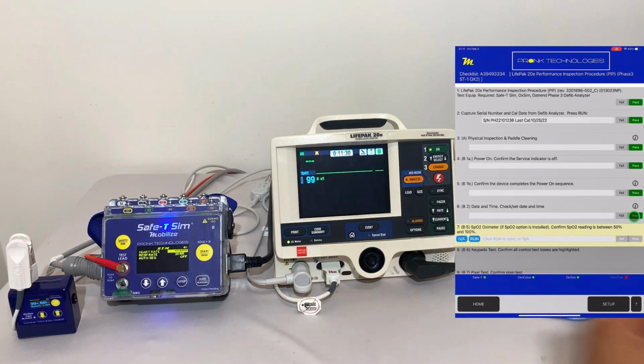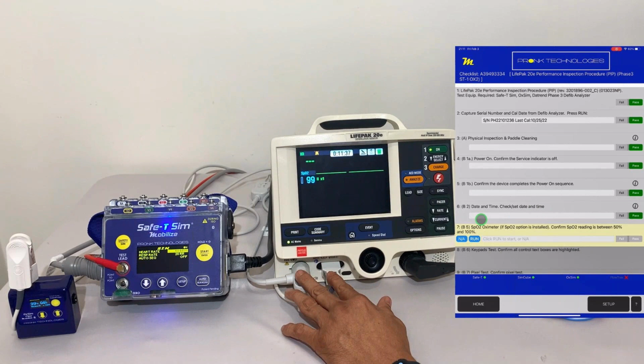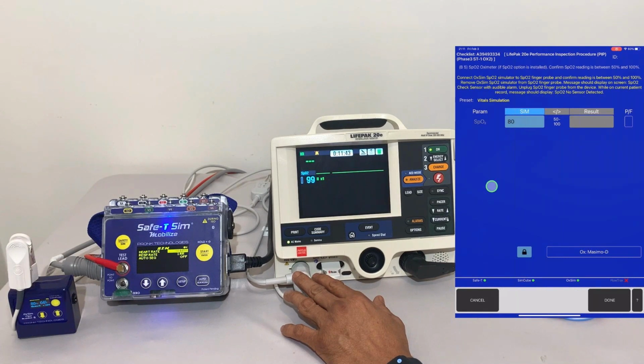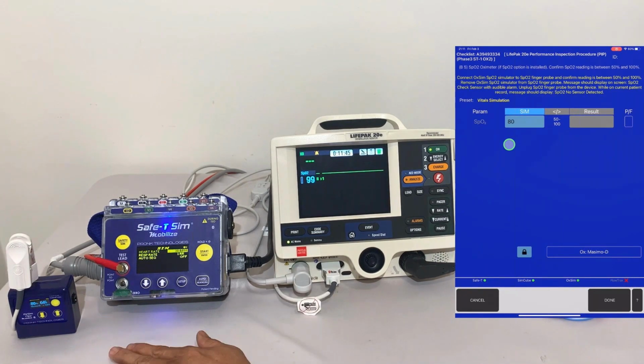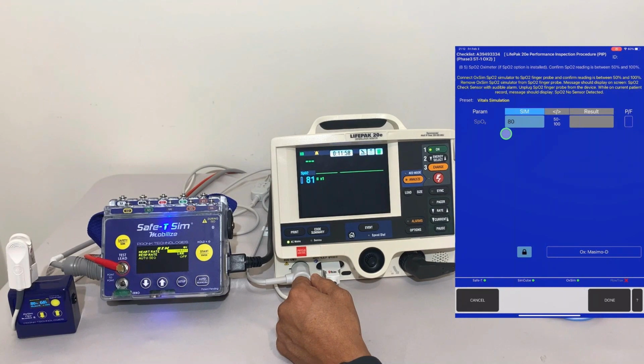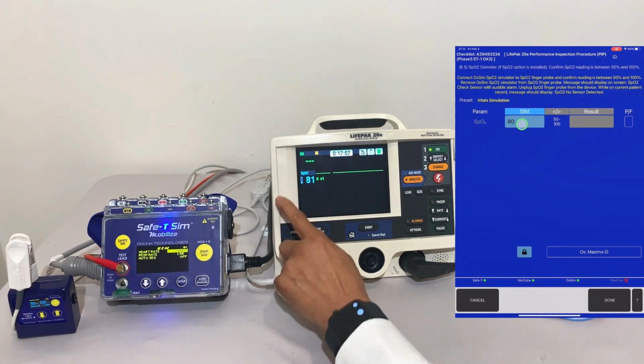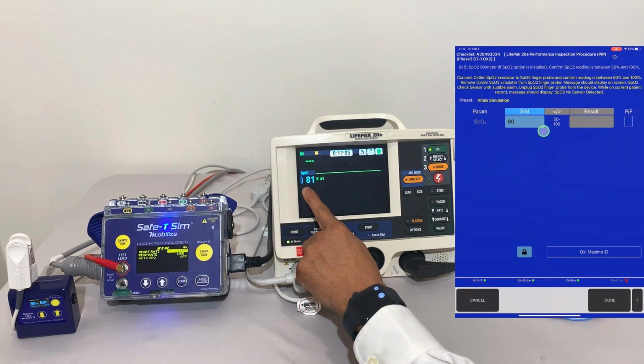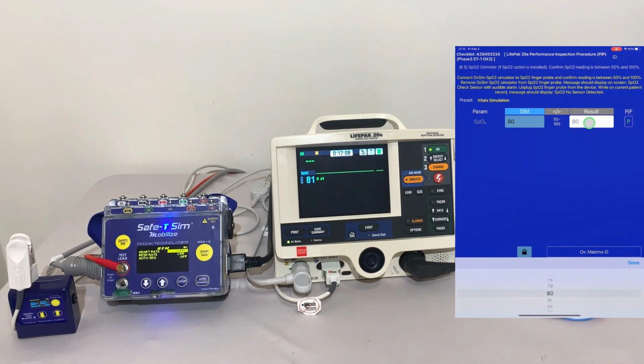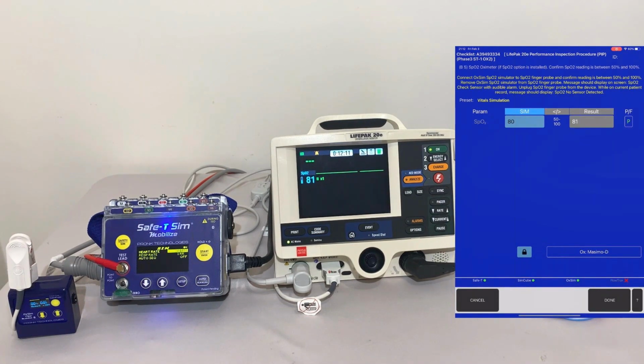The next step is to do a functional test for SpO2. This particular defib does have the SpO2 option. I need to confirm readings, so I'm going to run that test. In this case, we're going to utilize an Oxymplex SpO2 simulator. The manufacturer allows us quite a wide range for this test, but we want to use something precise to feel confident that our defibrillator is giving us good readings. We can see the target is 80. The measurement we're actually seeing on the defibrillator is 81. I tap on this field, scroll and select 81 to capture that result based on what we've set it to, and we can complete that step and go on to the next one.